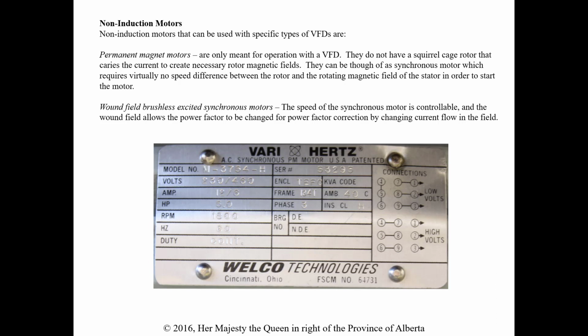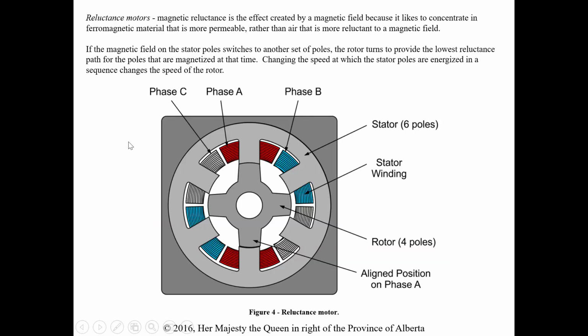Synchronous motors, the speed of a synchronous motor is controllable, and the wound field allows for the power factor to be changed for power factor correction. So that'd be an advantage. So again, just concentrate on the differences between all these motors in case it comes up as a question. Last one to talk about is reluctance motors.